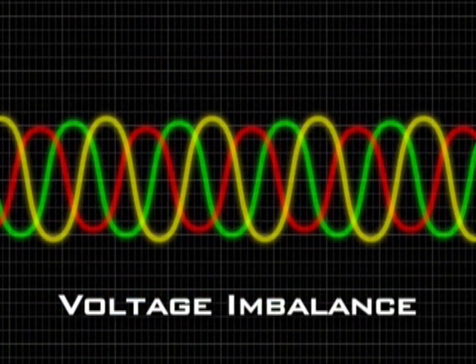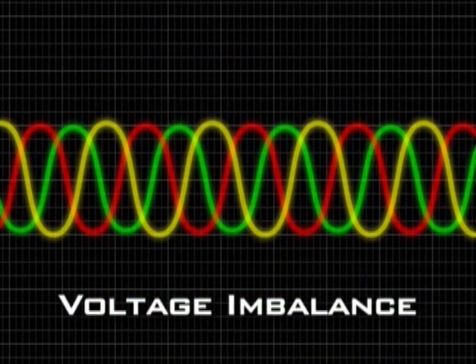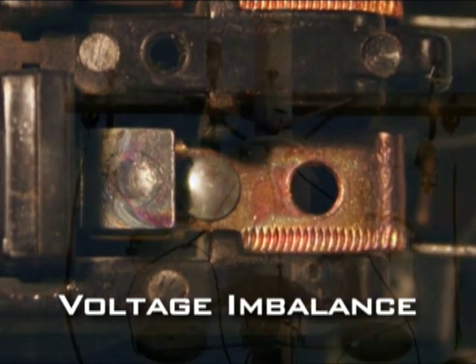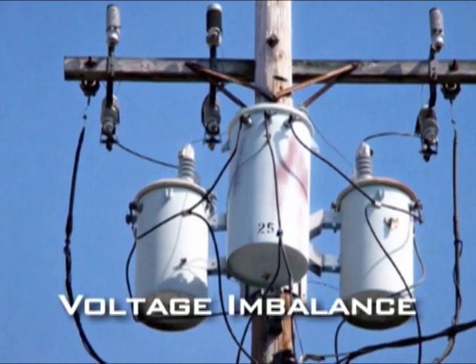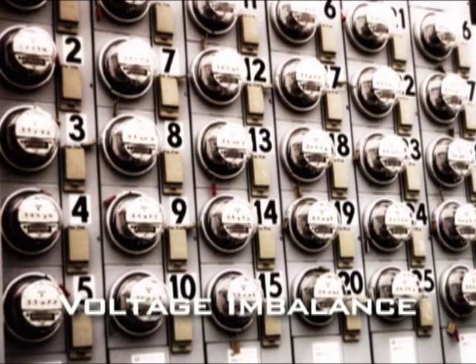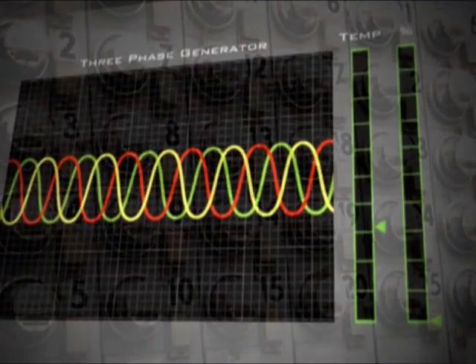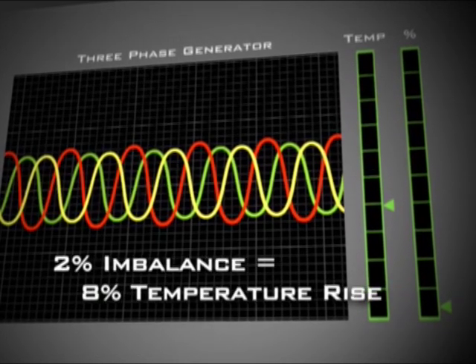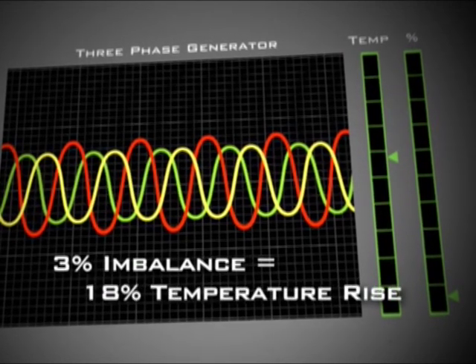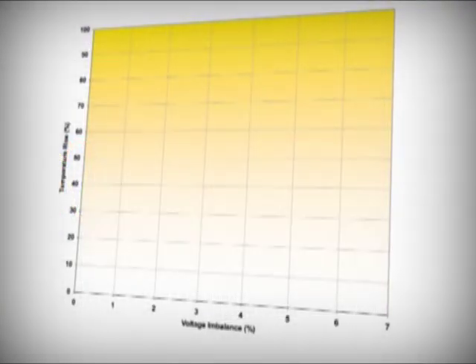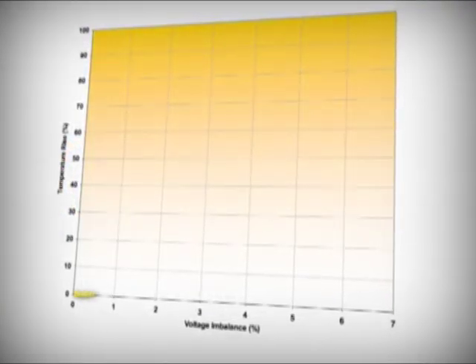The third and very common problem that threatens compressors is voltage imbalance between the three phases. There are several causes: a contactor becomes worn, a transformer fails and is replaced by a different current model, or a new load is added to one phase of the facility's power system. Even small voltage imbalances can be harmful. A two percent imbalance can cause the temperature of the motor windings to increase eight percent. A three percent imbalance can cause an eighteen percent temperature rise. The greater the imbalance, the higher the motor winding temperature and the sooner the insulation will fail.